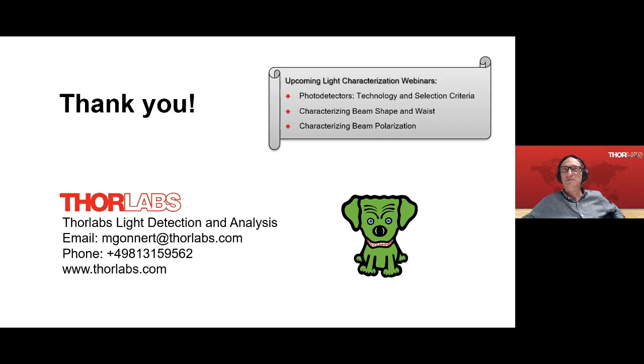If you have a higher power, is it better to rely on the sensor ND filter or to use a laser pickoff that picks off a small amount of laser power? Yeah, that's a good question. It depends, of course, on the power level. In general, especially absorptive filters can only handle a low power density. Reflective filters can handle a bit more, but in general don't exceed a power level of 1 watt, as a rule of thumb. So if the level is higher, take a pickoff.